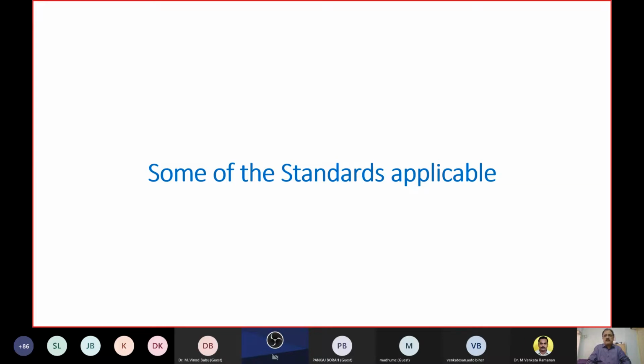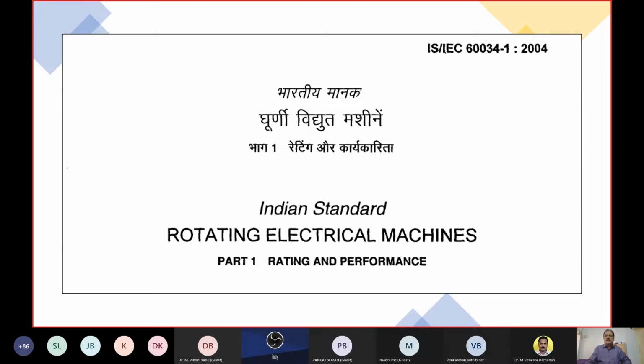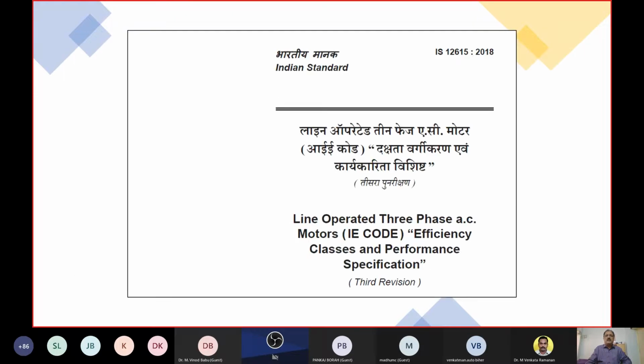These slides, I'm sure, will be made available to you by the organizers. If you require more input or want us to elaborate, we will be able to share, or it is also freely available from the internet. So we'll go ahead and see a few important standards that are used in the industry for applications. Like I mentioned, the dual standard IS/IEC 60034-1 2004 became the general standard for rotating electrical machines from the year 2016 or 17, if I'm not mistaken. Then you have IS 12615 2018, which is the latest edition, which includes IE2, IE3, and IE4, 2-pole, 4-pole, 6-pole, 8-pole, from 0.12 kilowatt to 1000 kilowatt in all the 4 poles.